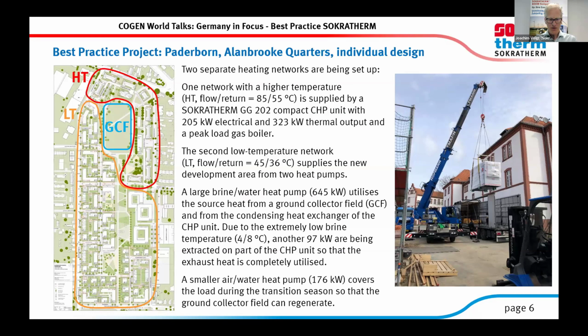A smaller air water heat pump with 176 kilowatt thermal output covers the load during the transition season. So the ground collector field can regenerate in that time and heat up again in the summertime. Regeneration of the ground collector field is always a very important thing.